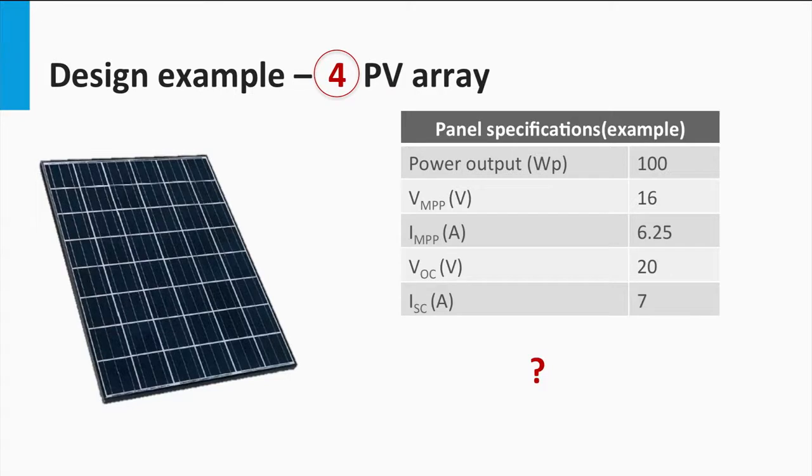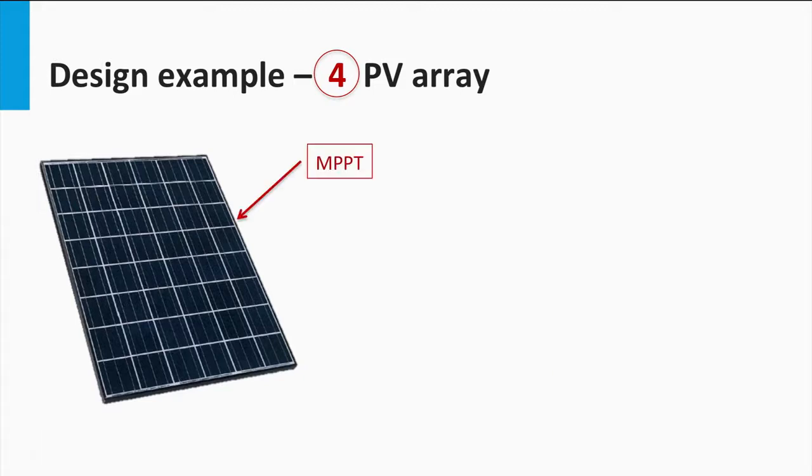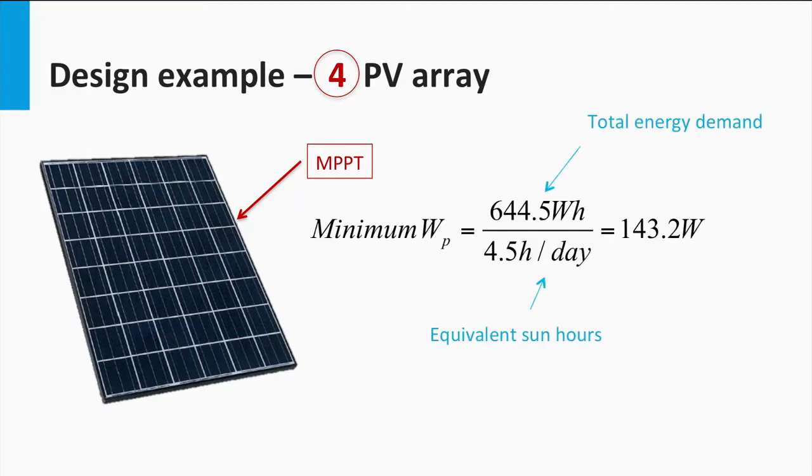Let's look at the electrical specification of an available PV module. It is a 100 Wp rated module with the given voltage and current parameters. Now, we need to find out how many of such modules are required to power the loads. Assuming that the panel would be operated at its maximum power point, we can find out the required number of panels as follows. We can first calculate the amount of minimum PV power required by dividing the total energy demand at the PV array output with the equivalent sun hours. Thus, the minimum PV power required is 143.2 watts.